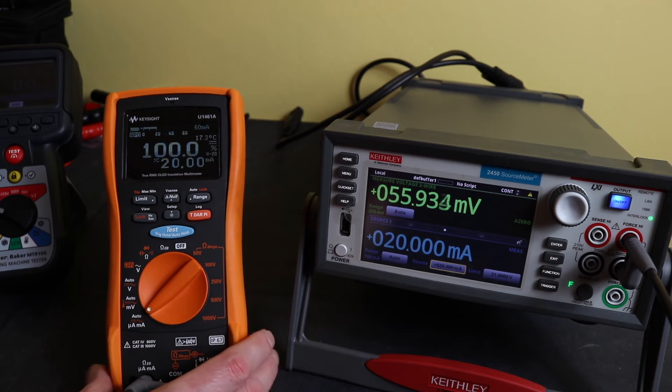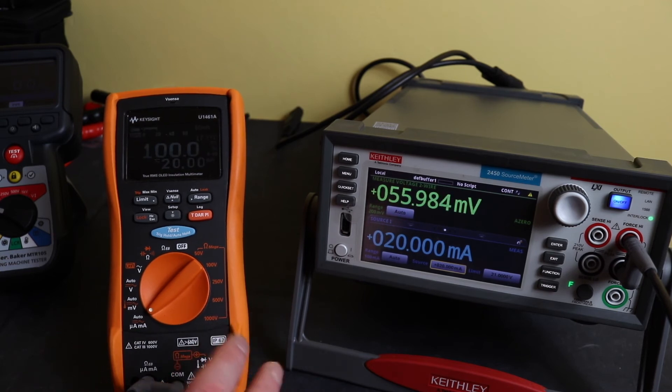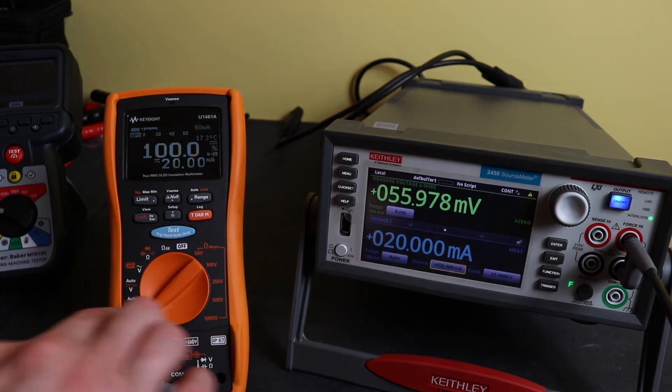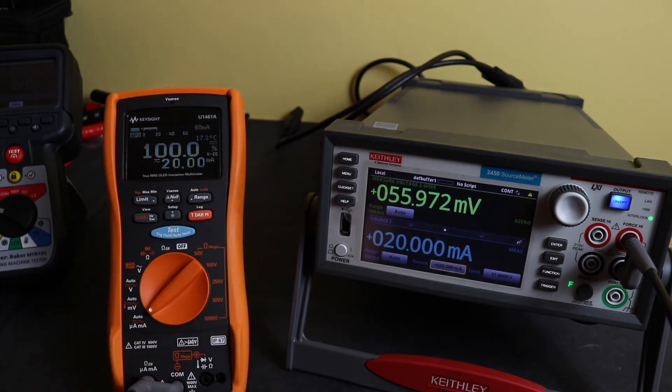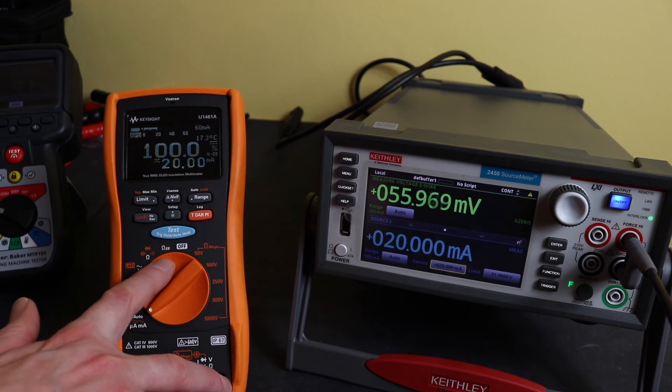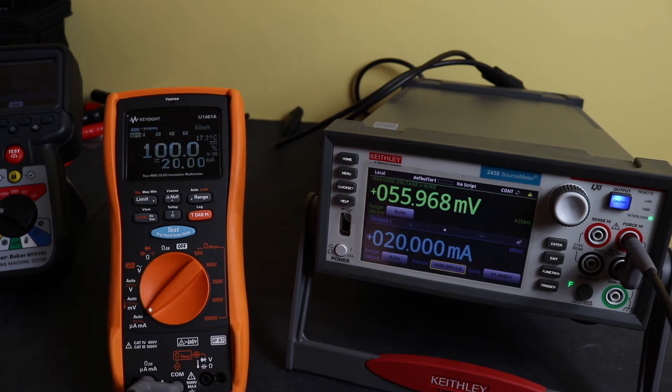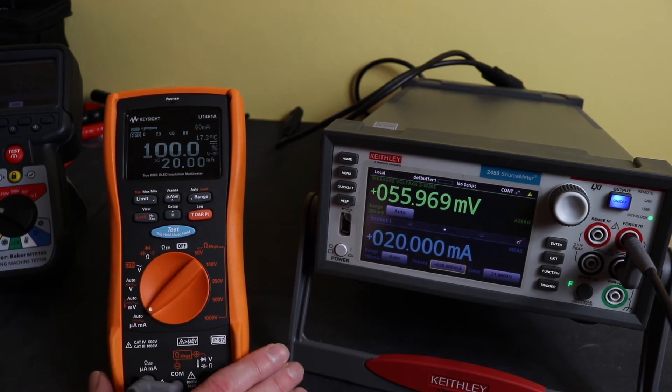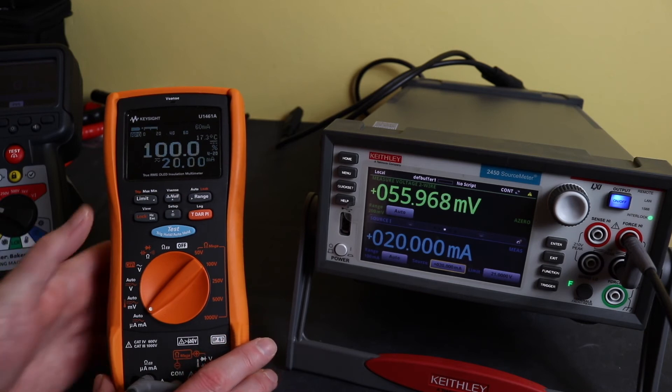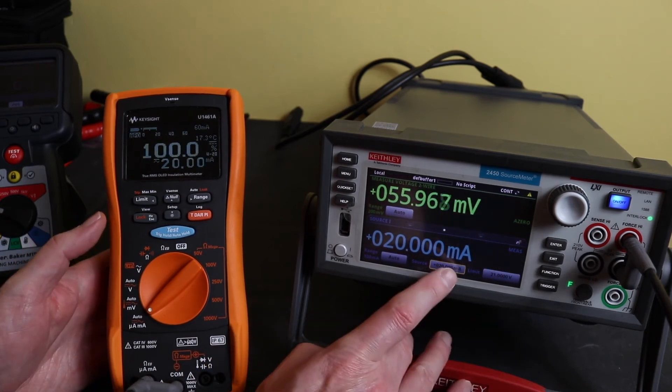So that's one reason why I like the Keysight so much, you see here superb accuracy when doing this particular test and I've got the insulation test function that'll work on the vast majority of motors without any issue and all the general the rest of the DMM functions are a 200 milliamp resistance test as well so very very good instruments for general purpose motor maintenance.